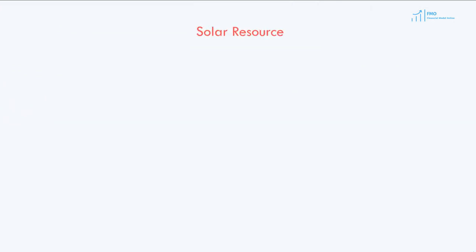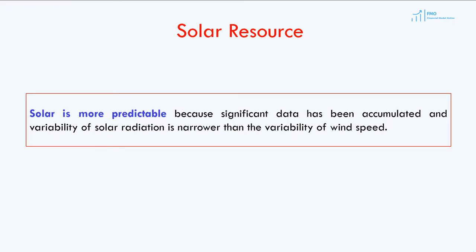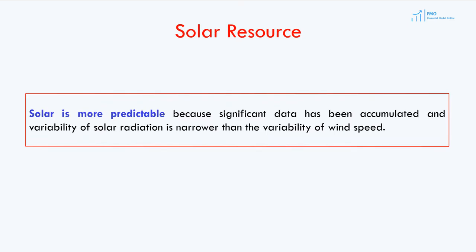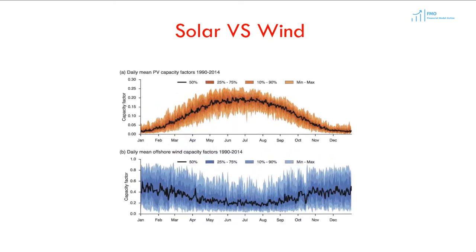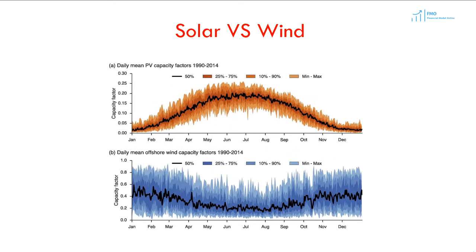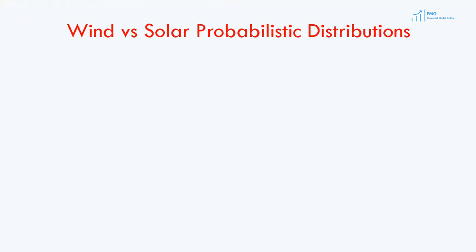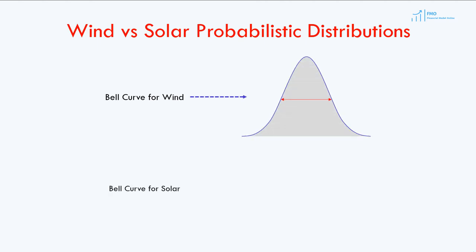Solar projects follow a similar process to establish the energy generation profile, except that there is significant data already available, and therefore it is more predictable. The variability of solar radiation is also significantly narrower than the variability of wind speed. The first graph shows the average capacity factor and its variability for solar projects. Comparing this to the wind project capacity factor variability, you can see how much wider the wind project's variability is compared to solar. This results in solar energy generation being more predictable, with a narrower bell curve, while the bell curve for wind is wider, reflecting higher uncertainties in wind energy generation forecasts.